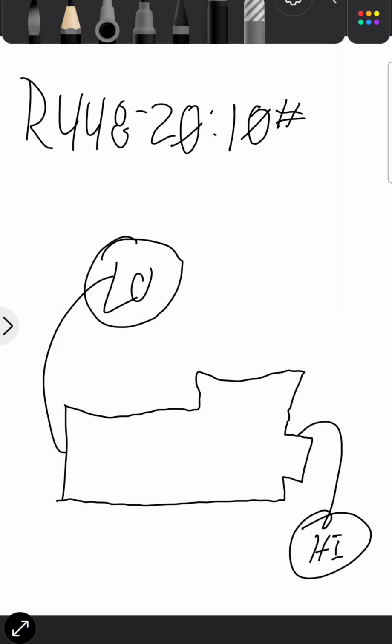Let's talk about, I would say, the two most common issues that I see when I have a low net oil, right? The first one is low oil, right? So if this is my sight glass right there, my oil is going to be below the sight glass and I have no oil. I can't see any oil in my sight glass, right? Where typically I want to see, for a Copeland compressor, like half to 3/4 sight glass, right?